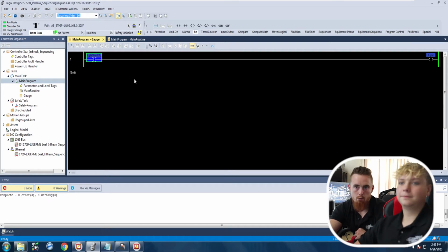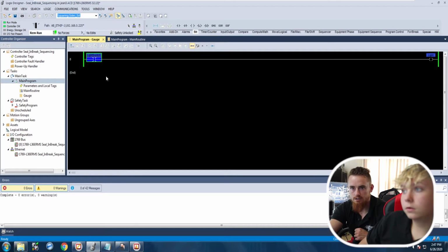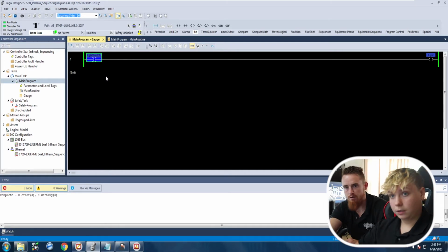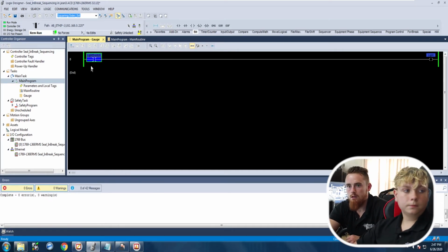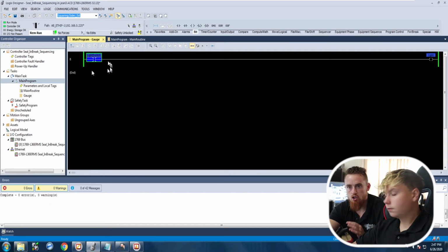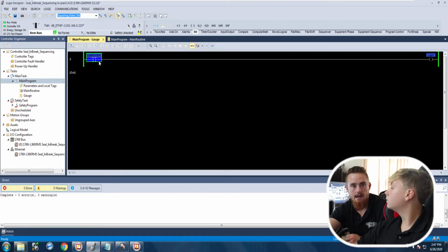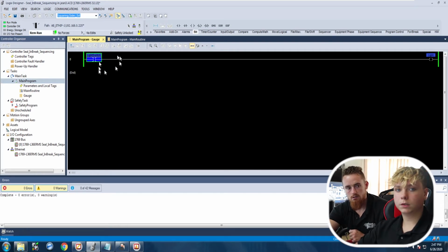And so, something I want to point out. See how when you press it fast, sometimes it doesn't show up over here? See how it's not showing up? So, Landon was just pressing that button real quick. A lot of the reason why you don't see it in the software is it's too fast for the software itself to update. So the PLC might be receiving that input. If you put a counter on it, it would still be adding up the counter, but the on and off is so quick that it just stays in off state. Does that make sense? Because this software itself is running slower.